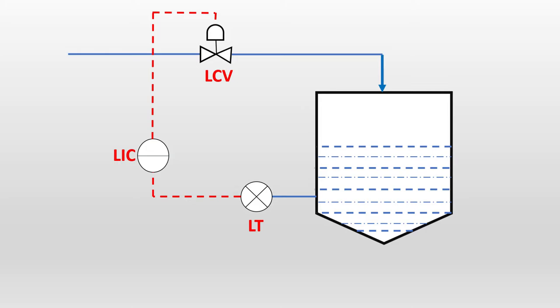The control valve operates to control the flow rate so that the level stays within the operating envelope. For example, if the level transmitter senses a low level, the Level Indication Controller signals the level control valve to open; if the level is high, it signals the valve to close so that it doesn't overflow. Basically, the level control valve throttles to control the process fluid into the tank so that the level is maintained.